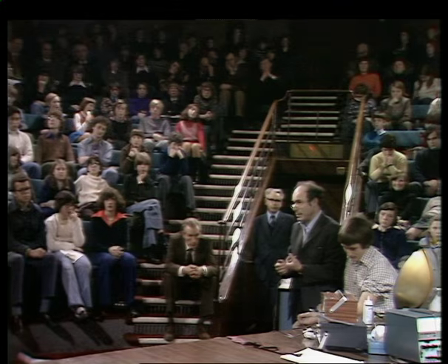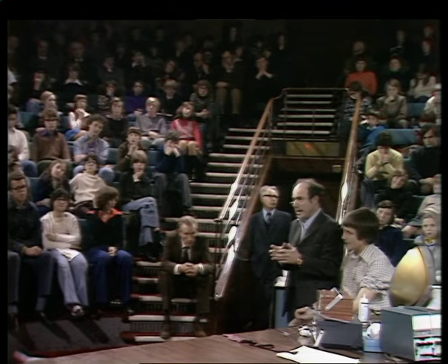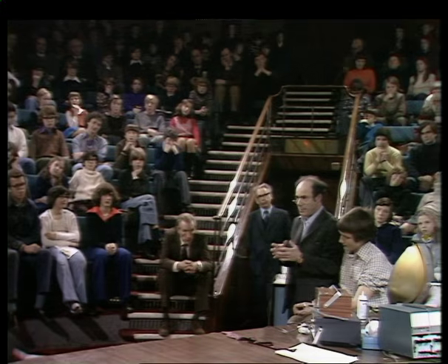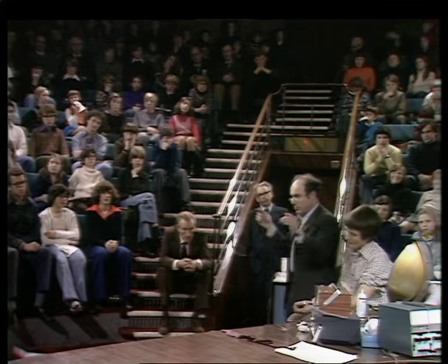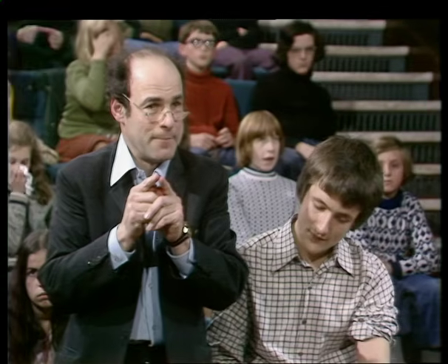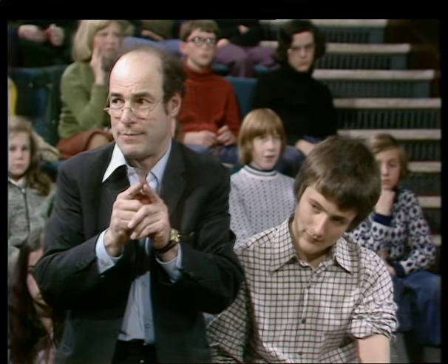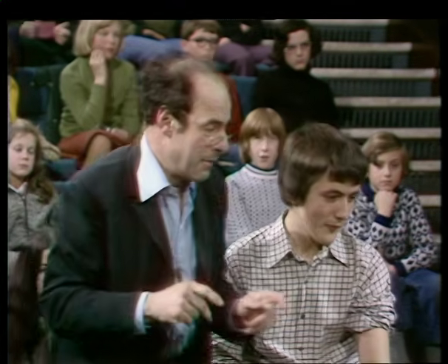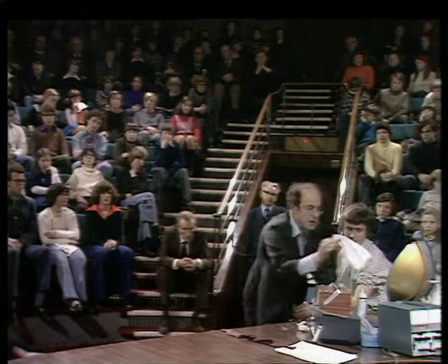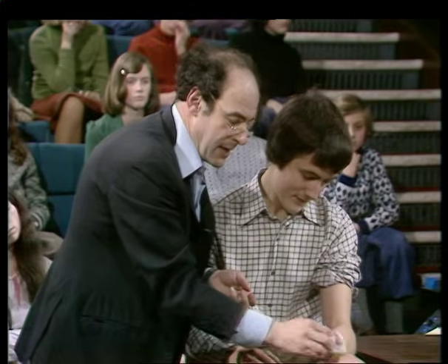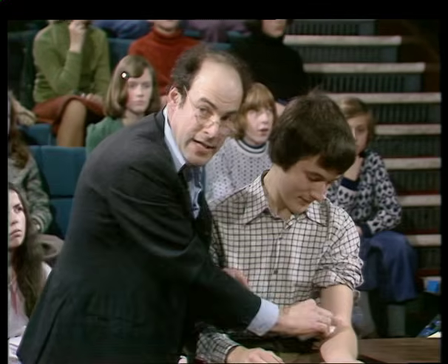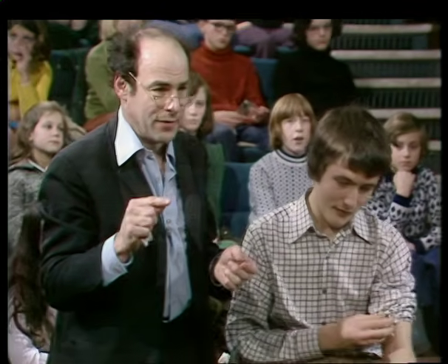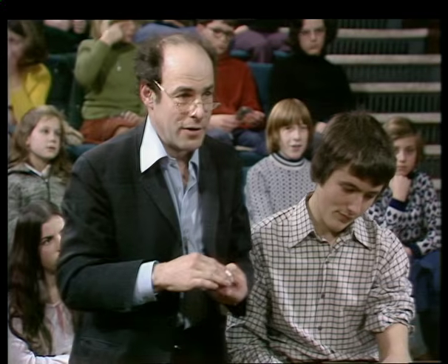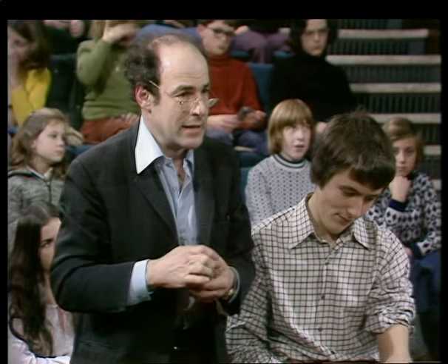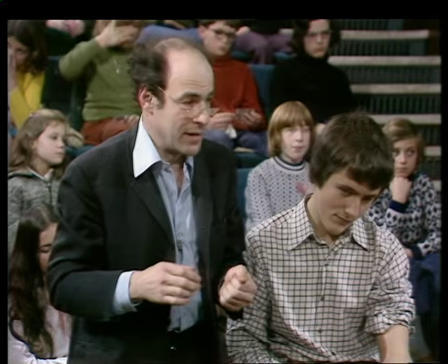And this is quite important, because the velocity of blood does by itself not tell us anything about how much blood is flowing, because a pipe could be this big, or it could be this big. The velocity could be the same, but the volumes which are actually being carried by the pipes could be very different. So one of the restrictions one must always remember in Doppler measurements is that one is measuring speeds, velocities, and not volumes, and that in themselves they can't be translated into actual flows unless one knows something also about the dimensions of the pipe through which the blood is flowing.